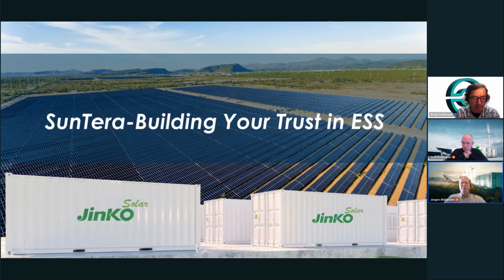Good question. We have a reference sensor to avoid false positives. On the other side, the logic behind the smart sensor also avoids false positives from light background gas. The Li-ion Tamer sensitivity is 1 ppm per second, and it's not just looking at a ppm level for high sensitivity, but also at the rate of rise of the gas signal, which is typical for an off-gas event.